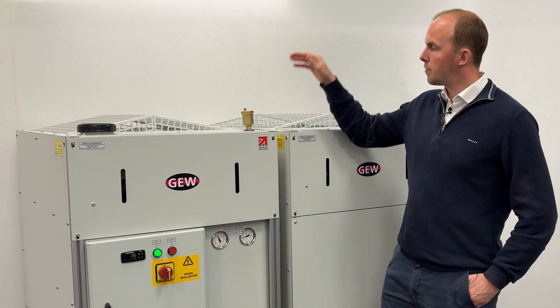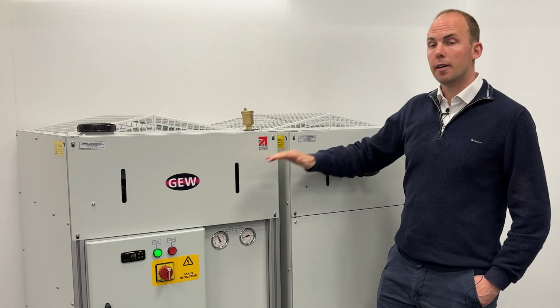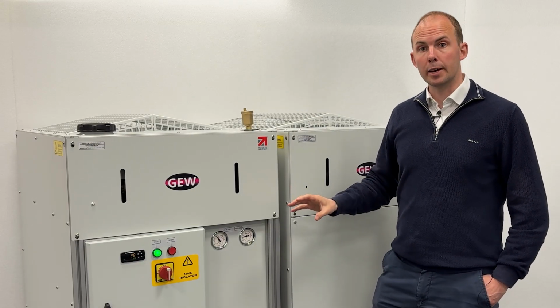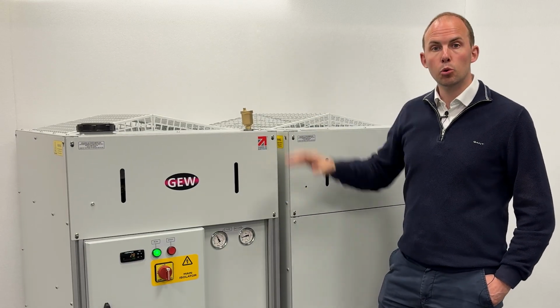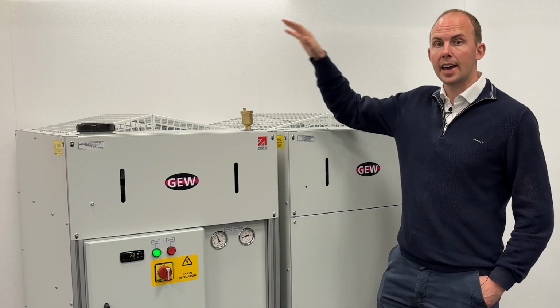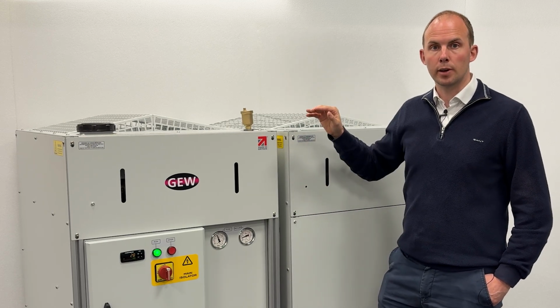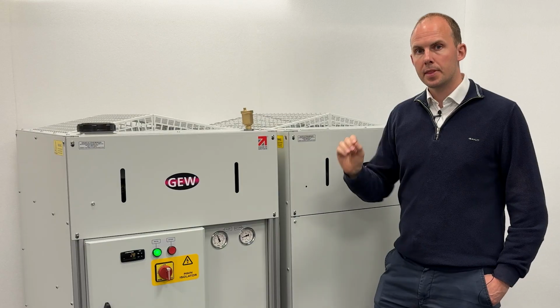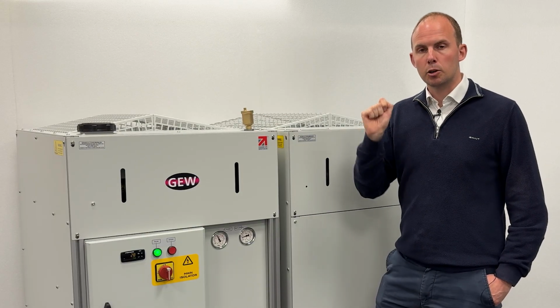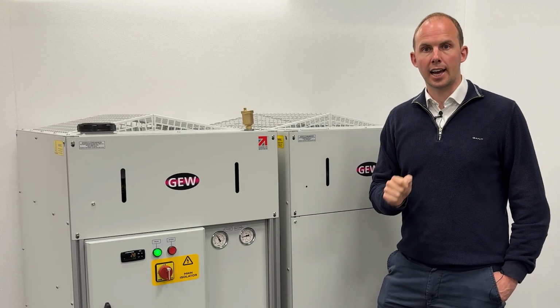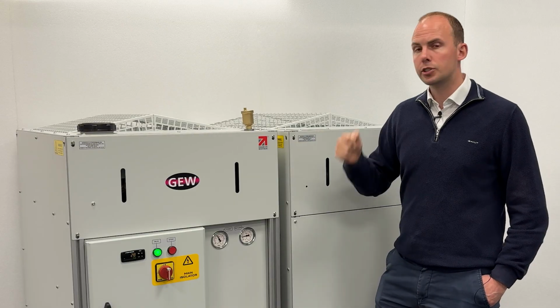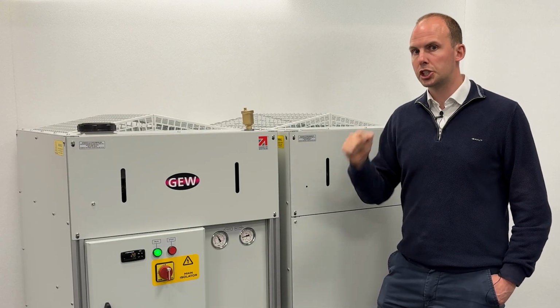It consists of a heat exchanger, a fan and a pump only, and cools the water using the ambient air in a factory. Importantly, these don't contain compressors and refrigerant gases or hydrofluorocarbons like we see in traditional chillers.